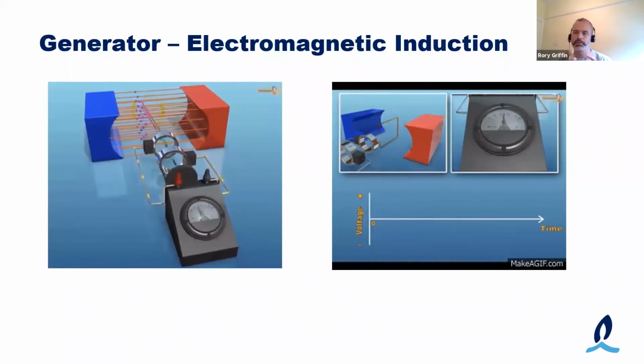So other bits and pieces with the generator: if the grid, for example, wants Whitegate to produce megavars lagging, the operator can increase the field current. So the excitation increases here and you'll over-excite the machine. If you need to do the opposite, where maybe at night time you need to bring down the voltage, say in the Cork area where Whitegate's connected, the operator will reduce the excitation, the machine will become under-excited and you'll start to pull megavars in.